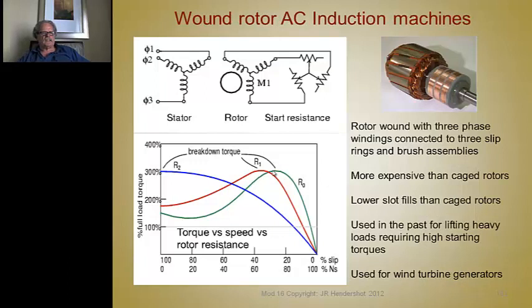So this is a picture of a little induction rotor with a wound field and 3 slip rings on it. And here's an example of what the torque speed curves look like, with what happens to the slip and what happens to starting torque. This green curve has the lowest starting torque, but it has the lowest slip, so it runs at the highest efficiency if it's running up here. And that's the breakdown torque.